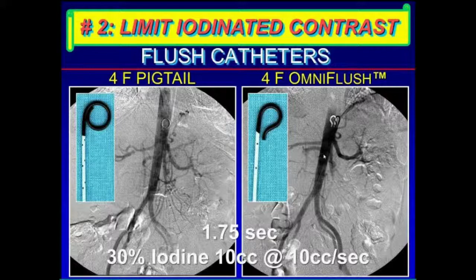This was after angioplasty. You can see the vessel is wide open, but you can also see that with no reflux, the same amount of contrast and at the same time in filming shows a much denser concentration of contrast in the region of interest. And that's what it's really all about. So with the OmniFlush, you could inject the same or less contrast as with a conventional catheter, but see the area that you needed to much better because there was no reflux into unintended branches and better concentration.